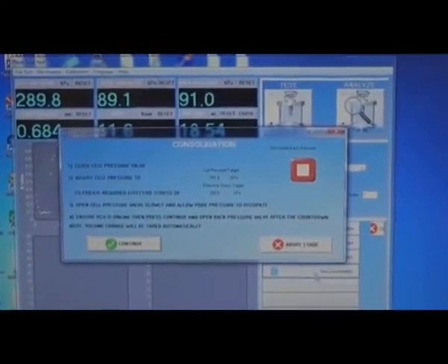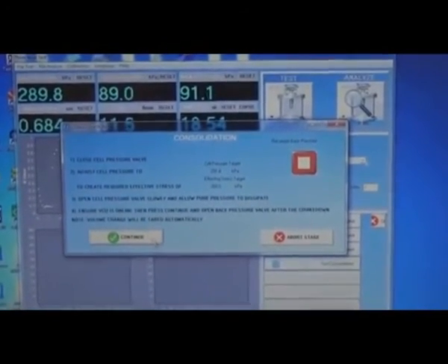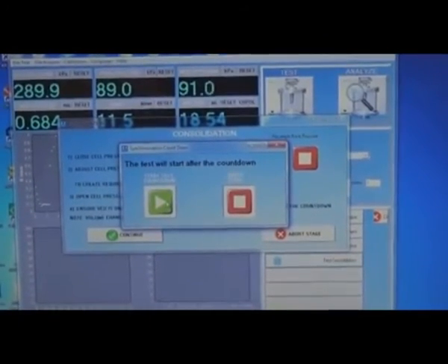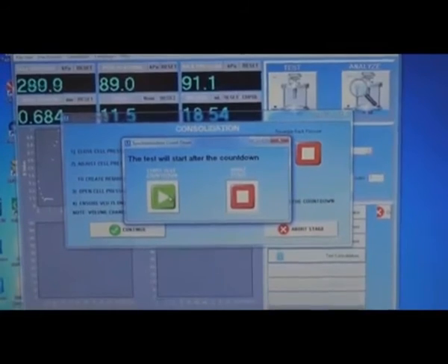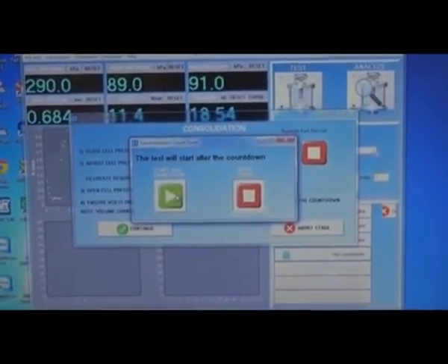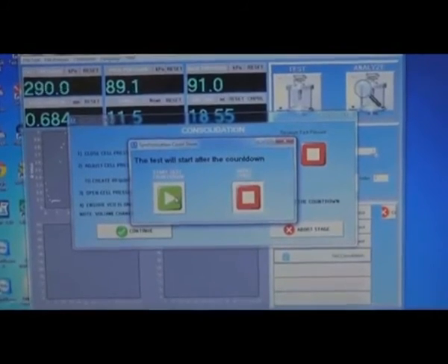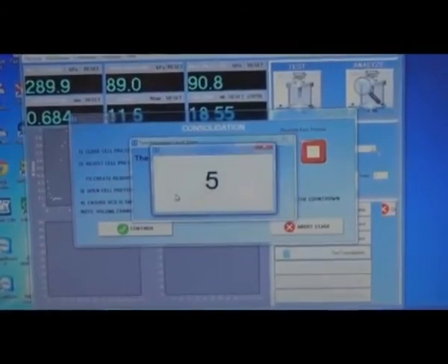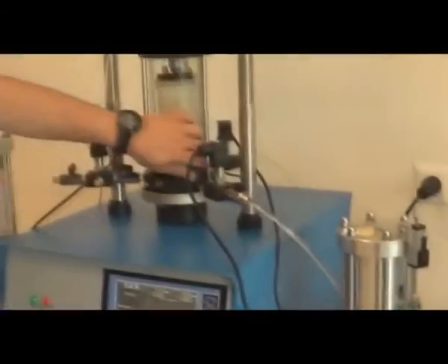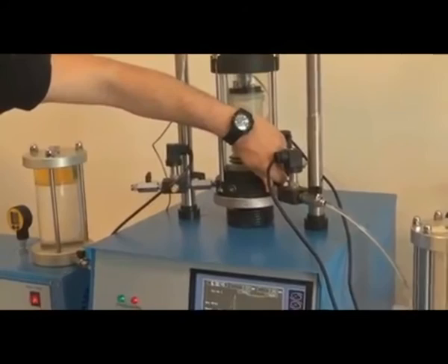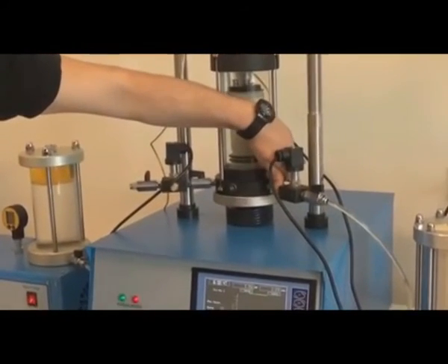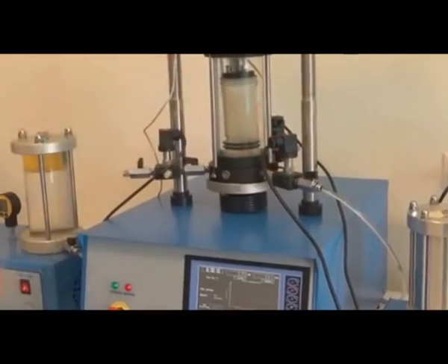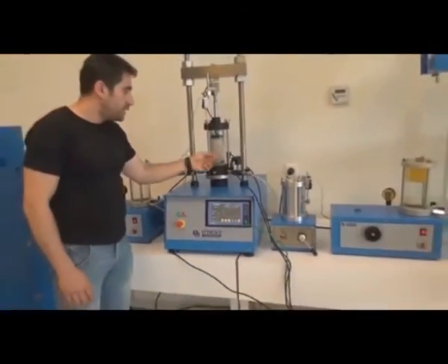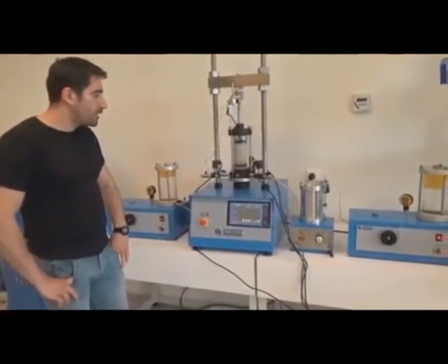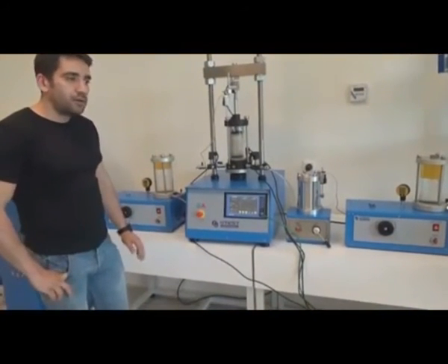Cell pressure is set to 290 kilopascals. We are going to click the continue button, and press the test countdown, and as the countdown stops, we are going to open the cell pressure valve slowly. 3, 2, 1, and we are opening it. Now we have increased the cell pressure to 290 kilopascals. We are going to wait a little bit for the pressure values to equilibrate.